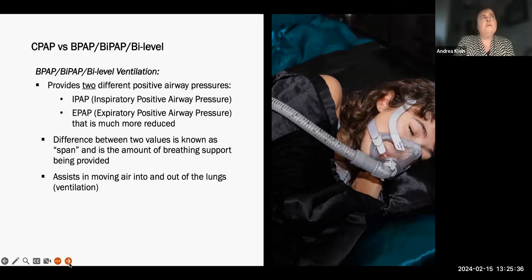For example, say you're prescribed an IPAP of 12 and an EPAP of 6. According to some schools of thought, that would be low span. Higher span is generally 10 points between those two values or higher, so one example would be an IPAP of 18 and an EPAP of 4. We are all different, so it's really hard to say which one is better or appropriate for you, because there's so much difference from person to person.